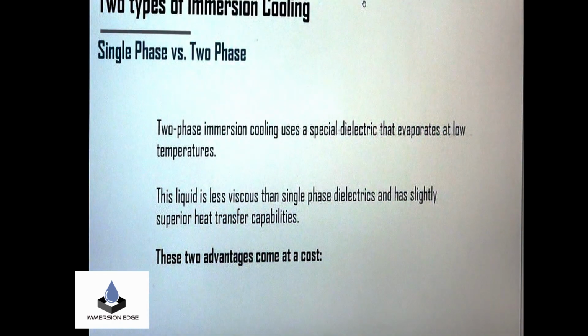So there are two types of immersion cooling: single phase and two phase. We use a single phase dielectric, proprietary fluid, but a lot of you may have heard of two phase. Two phase immersion cooling uses a special dielectric fluid as well that evaporates at low temperatures, but this liquid has a lot of advantages and disadvantages.